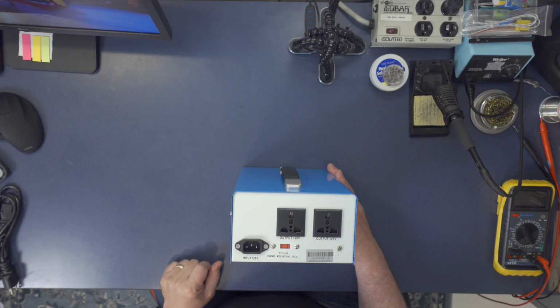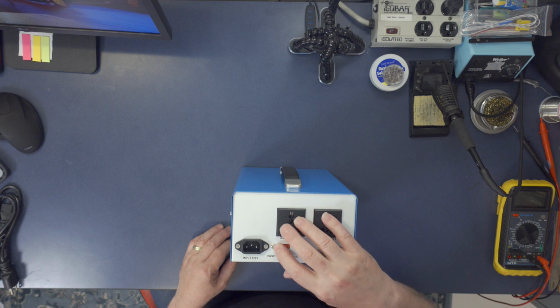We got our IEC connector. It has this mode switching here, which says standard and special. My understanding is that it switches between what would be a medical isolation transformer, which just isolates for noise and carries the chassis ground through from the isolated outputs through to your mains, and it's really just there to deal with line noise, etc. It also has the special mode, which does not carry that ground through, and that's what we call a tech level isolation transformer, where the ground does not continue through the device under test to earth ground.